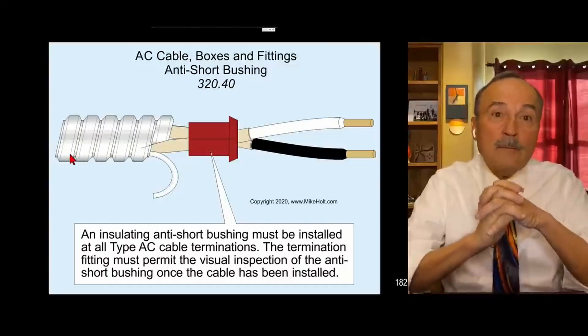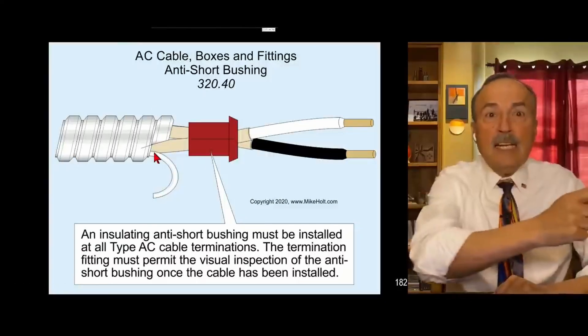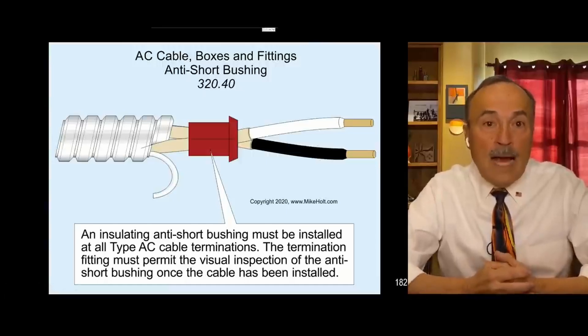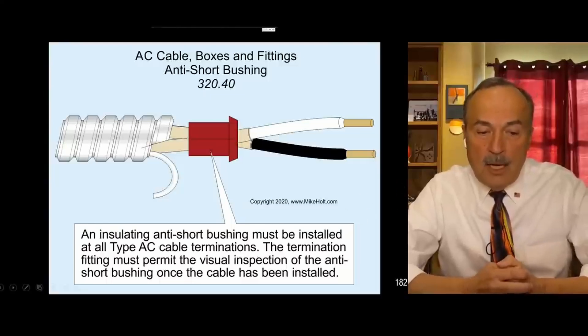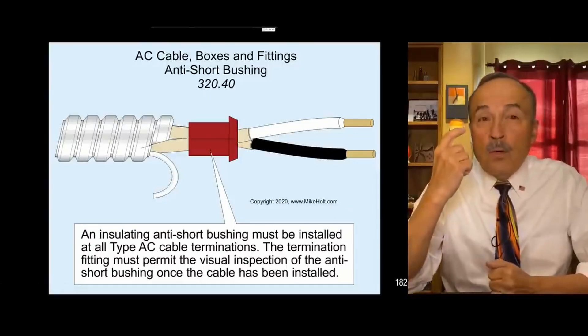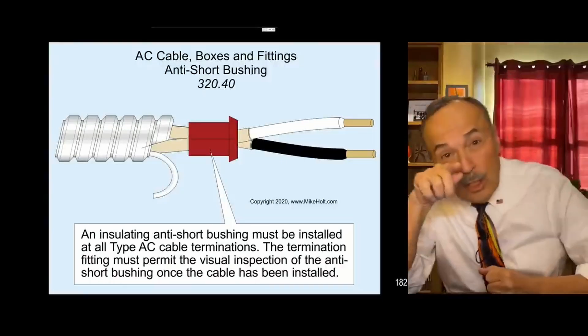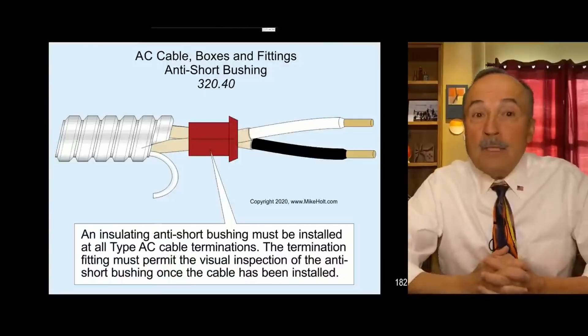Cut the bonding strip off, take the anti-short bushing, stick it in there. NEC 320.40 requires it: an insulating anti-short bushing must be installed in all type AC cable terminations. The termination fitting must permit visual inspection of the anti-short bushing once the cable is installed - per 110.15, you have to use a fitting specifically listed for armor cable so you can see the anti-short bushing.